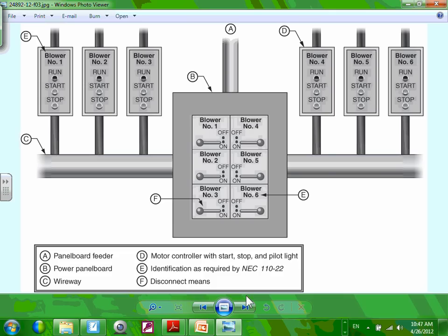I usually don't touch on it, but Cutler-Hammer has a really nice sheet in their consulting manual that can size a VFD for you, based on whether it's variable torque or constant torque, and of course the voltage and the horsepower. But you need to ask them whether you have variable torque or constant torque on this motor, a fan being variable torque. So there's a lot to it beyond just electrically speaking. I can show you where in Cutler-Hammer you do them.